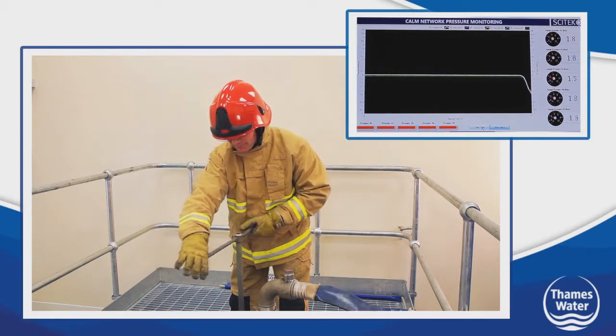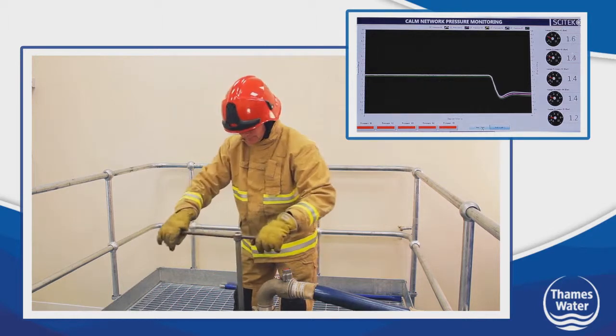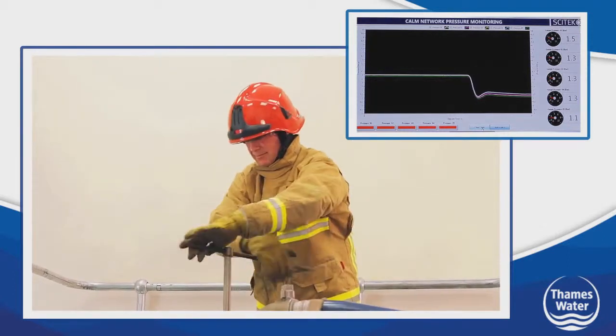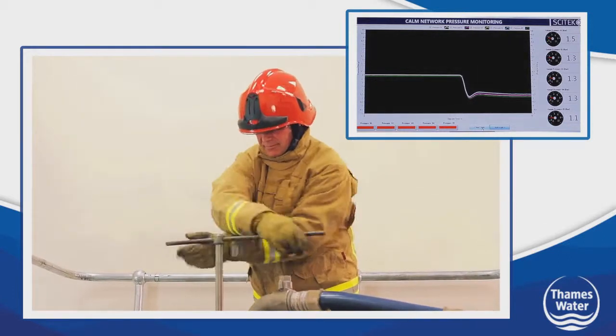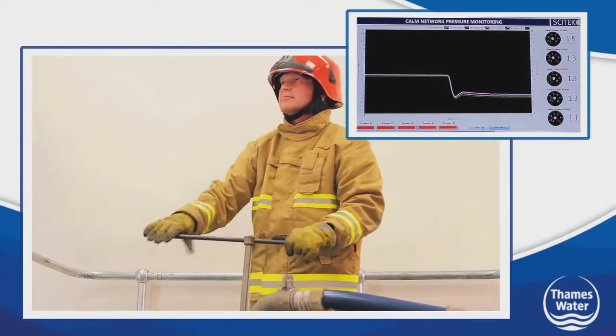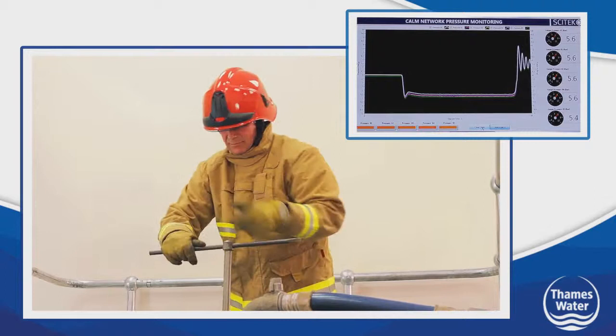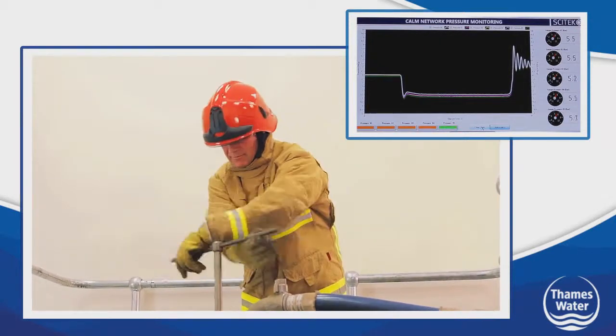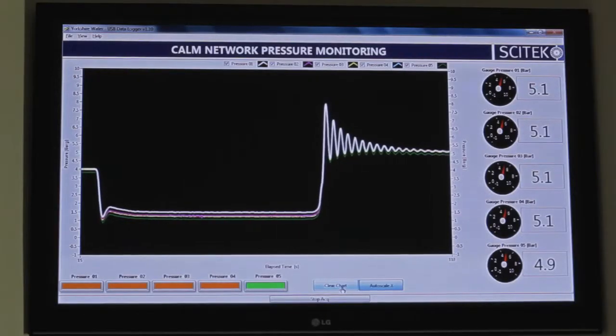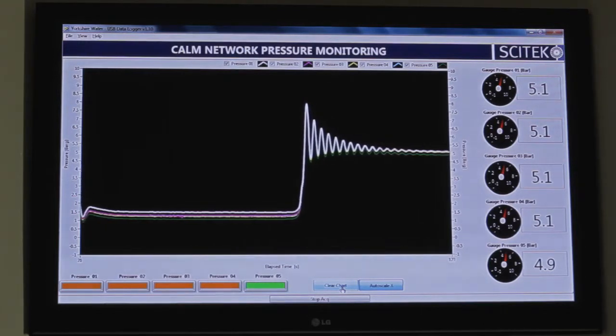Here we have an incorrect way of how to operate a hydrant, perhaps how you would currently operate one. Note the spike on the screen, which is capturing the surge effect. Potentially, most damage is caused when closing a hydrant too quickly. You will notice the ripple effect, which means the surge is not just a single action, but an ongoing factor until the system settles down.